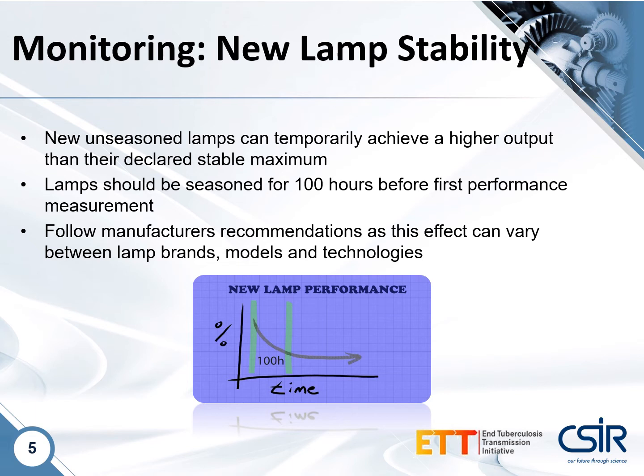Of course, you should always follow the manufacturer's recommendations, as this effect we're talking about can vary between brands. If the manufacturer, however, gives no information on this, ensure that you're applying 100 hours of seasoning before your first measurements.